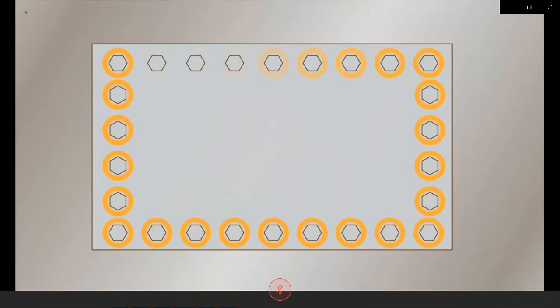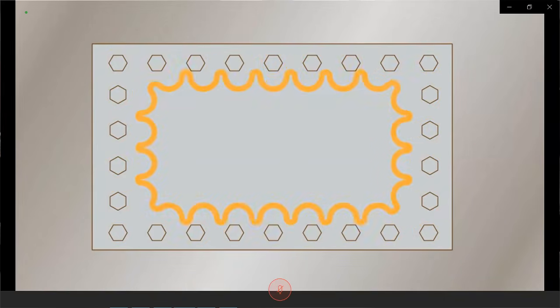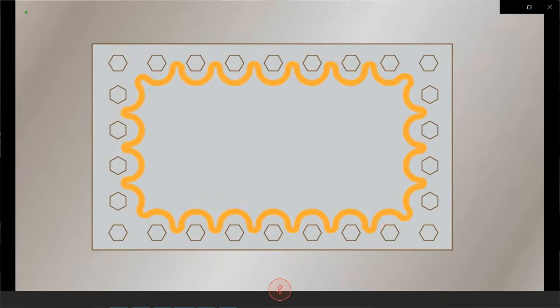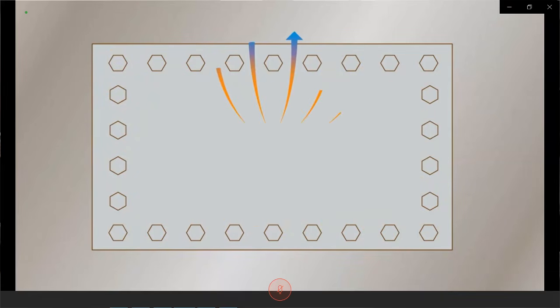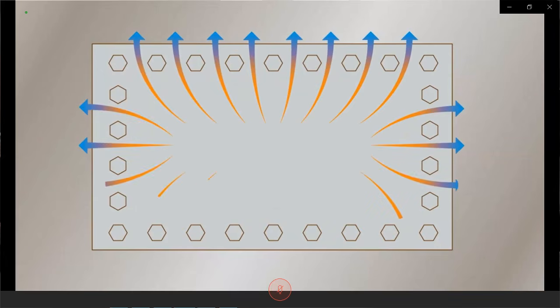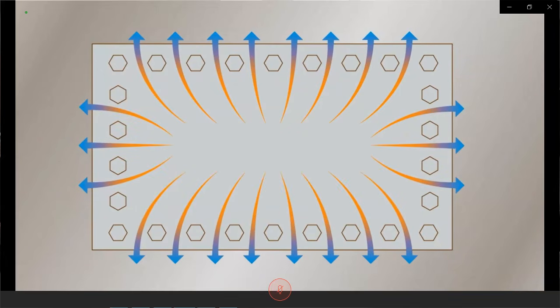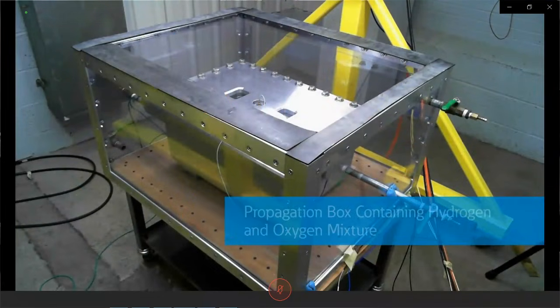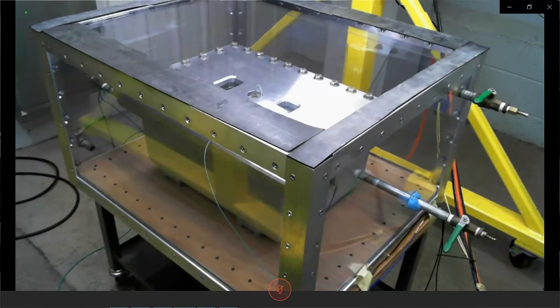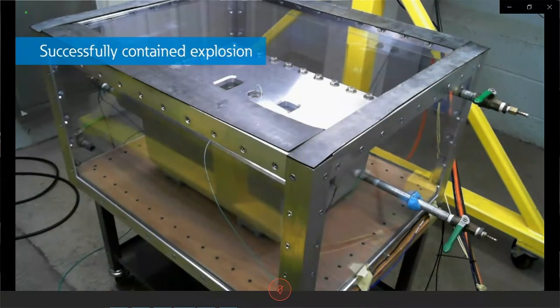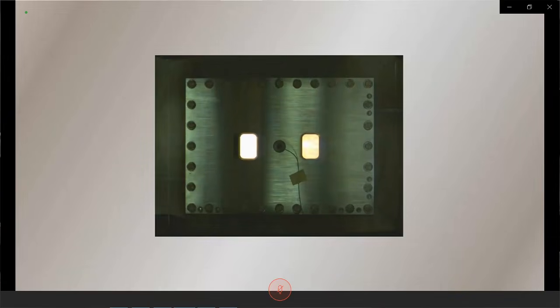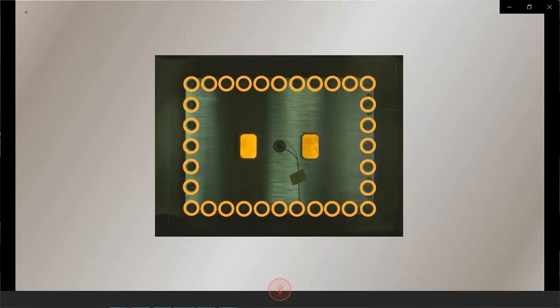Traditional NEMA 7 enclosures are designed with a significant number of cover bolts. When fully engaged, these bolts apply even pressure around the enclosure's flame paths, allowing heat from an internal combustion to be transferred evenly over the paths and released safely back into the atmosphere. This test, conducted at Eaton Crouse-Hinds Business UL Certified Lab, shows a traditional NEMA 7 enclosure successfully containing an internal combustion, cooling the explosive gases, and preventing the outside hazardous atmosphere from igniting. Watch again in slow motion as the enclosure withstands the combustion forces and cools the explosive gas by diverting it through all the engineered flame paths.